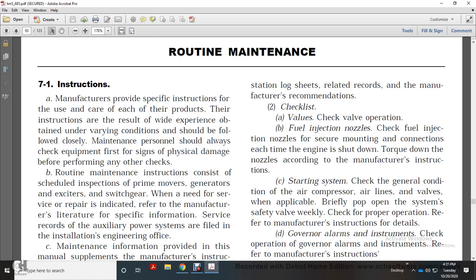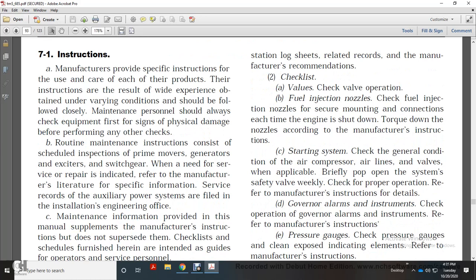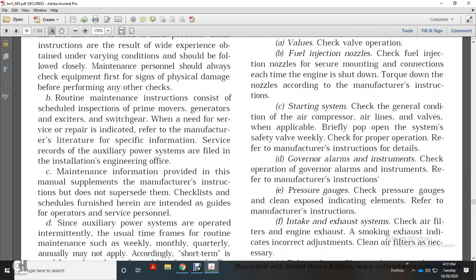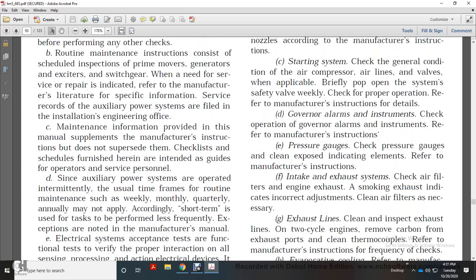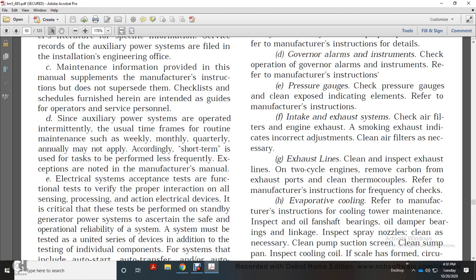Starting system: check the general condition, air compressor, airline valve, and where applicable briefly open the system safety valve weekly. Check for proper operation, referring to manufacturer instruction detail: generator, governor, alarm and instrument. Check operation of the governor, alarm and instrument, referring to manufacturer instruction. Pressure gauge: check the pressure gauge, clean, and exposed indicating elements, referring to manufacturer instruction. Intake and exhaust system: check the air filter and engine exhaust. Smoking exhaust indicates incorrect adjustment. Clean air filters as necessary.